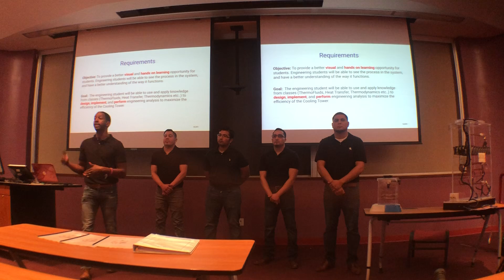Cooling towers are categorized by their design features. Natural draft cooling towers use air buoyancy to facilitate air travel. Mechanical draft cooling towers use a fan or blower to introduce air into the system. Cooling towers with fluids flowing perpendicular to each other are considered crossflow, and those with fluids flowing in opposite directions are considered counterflow.